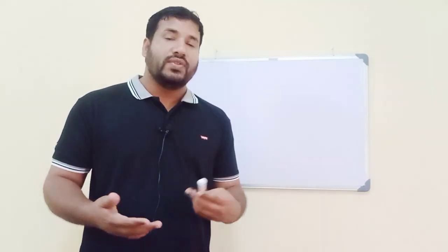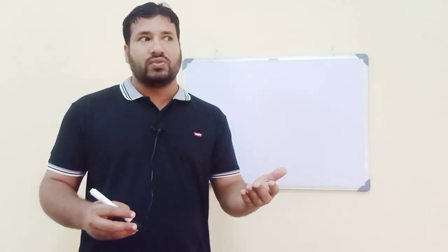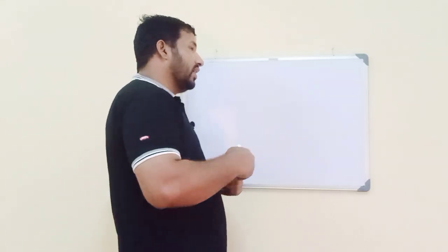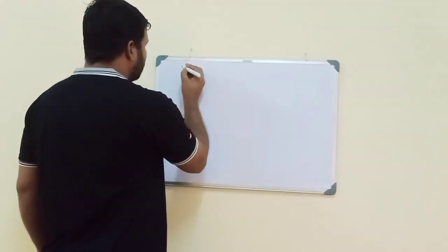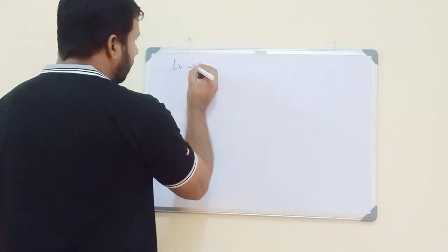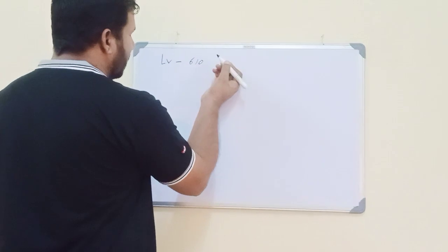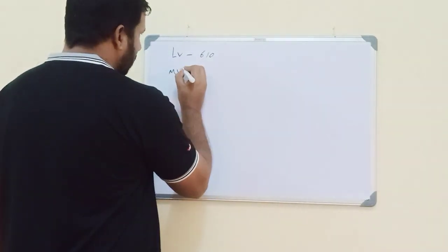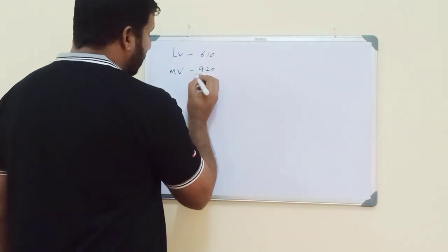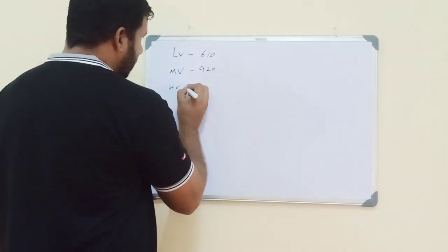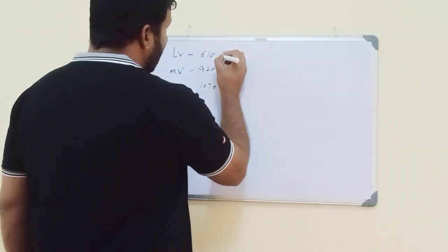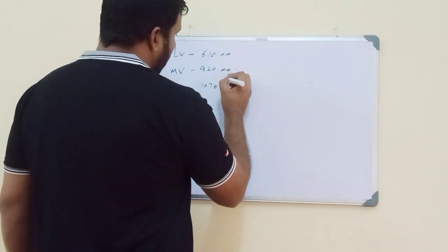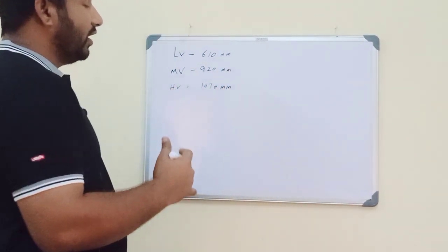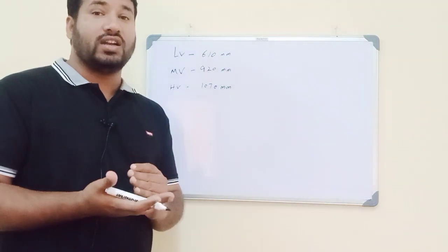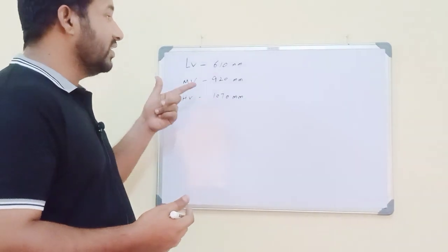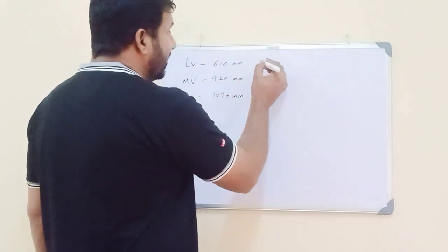But in Aramco, there is some difference. If we go to the low voltage, I'll just write it so you can see. LV cable direct buried depth is 610 mm, MV is 920 mm, and HV is 1070 mm. This is all in mm. This is basically the depth of cable, meaning when we make a cable trench, we have to make sure the depth of the cable is this much. When we go to conduit, there is a difference.